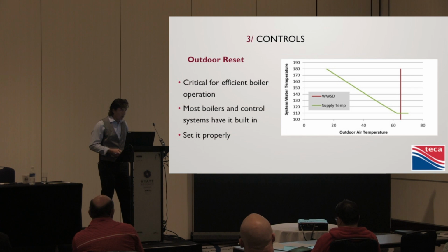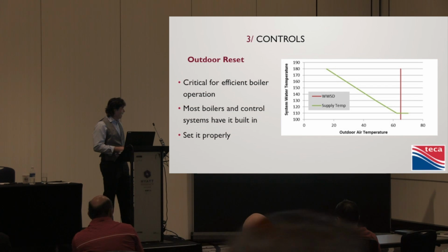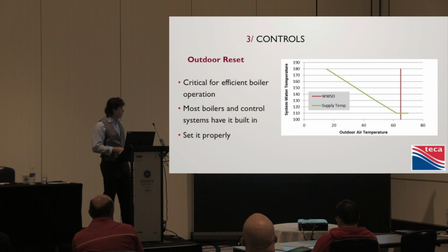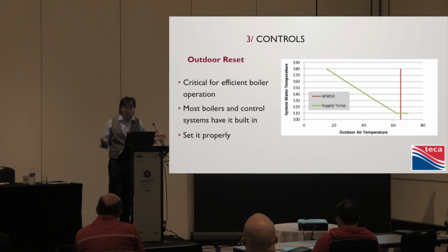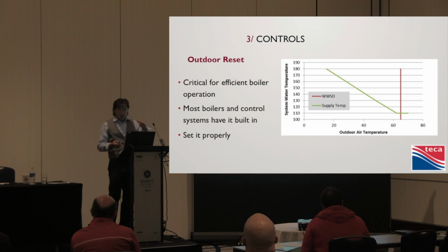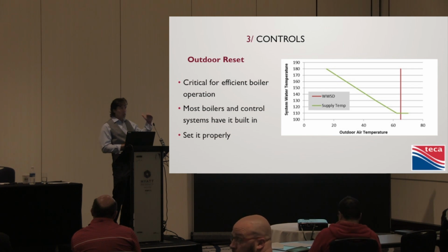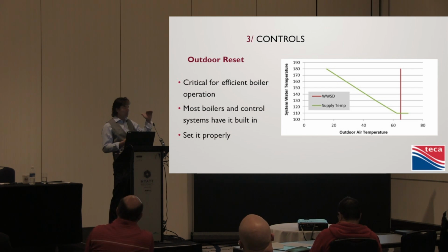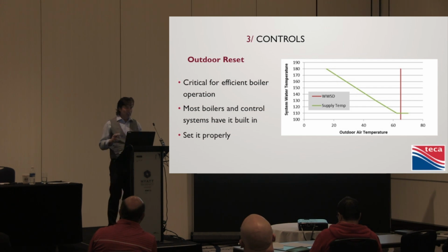So when you set up the boiler, don't set it at 130 and forget about it. You've lost all the efficiency. You've got to set up the warm weather shutdown. And that means dialing in the minimum supply water temperature. So if we're doing a radiant system, it's going to be 75 F. I mean, if it's 70, the same temperature as the room, it's probably not going to heat much. 75, let's say you start out, and let's say the maximum, depending on your load calculation, is 125. So that's your range. So you would start here. So you go 70 to 125, and that would be what's called your reset curve.